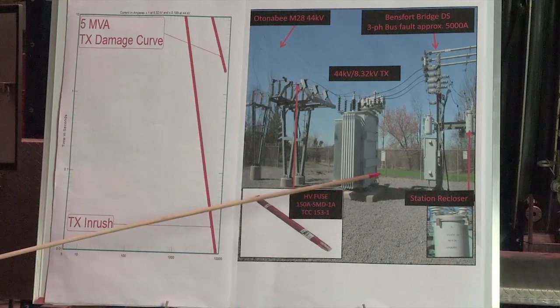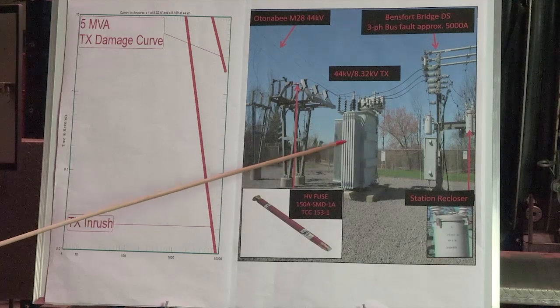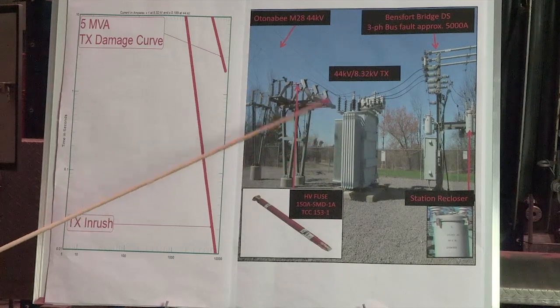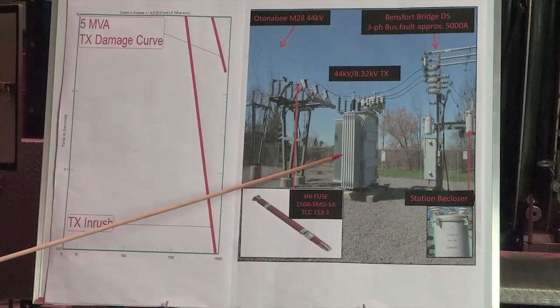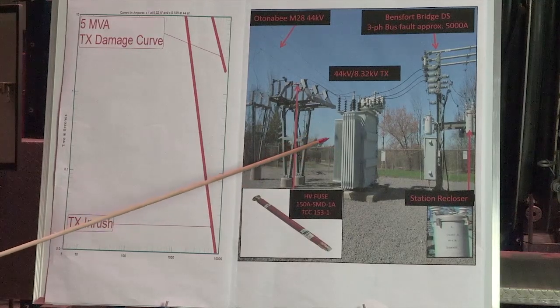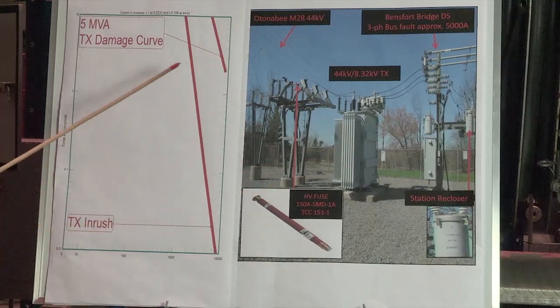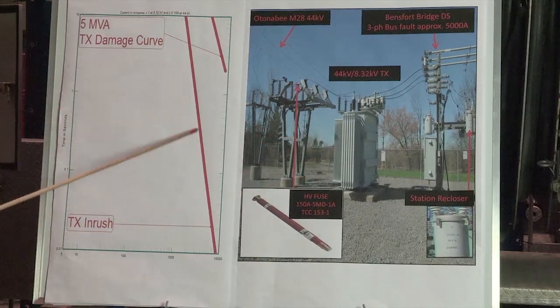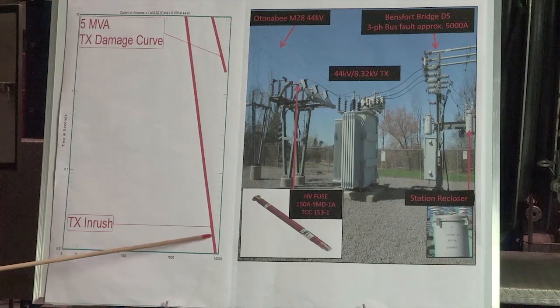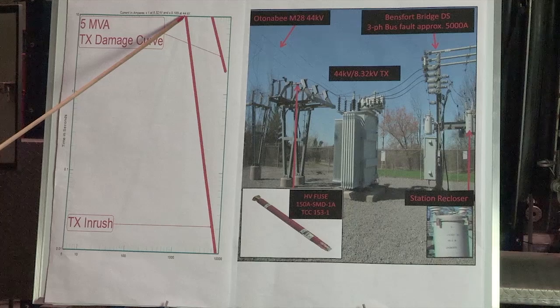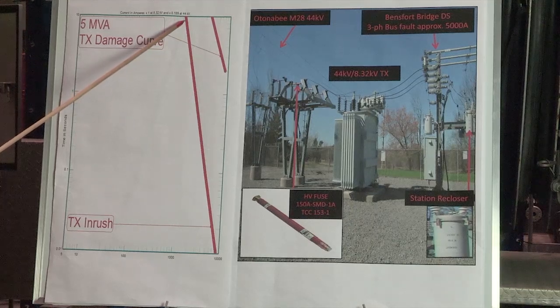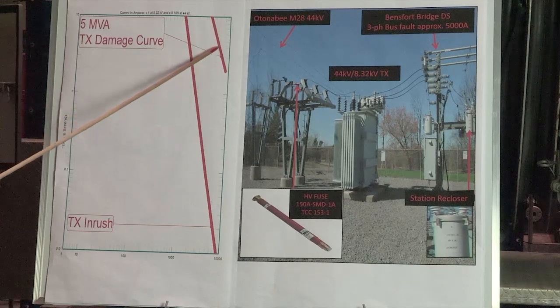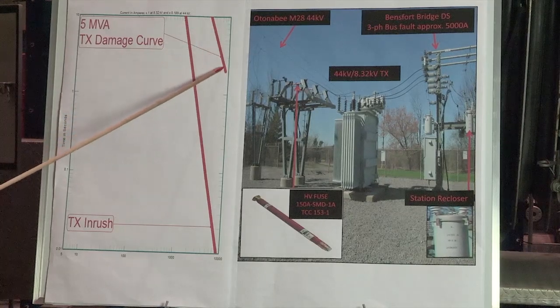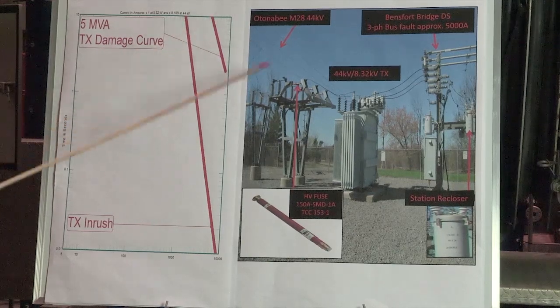So starting at the distribution station, we have Bensford Bridge DS. Now we're going to have to model in this transformer into a program that is called TCC, Time Characteristic Curves. So the diagram beside me is showing the transformer modeled into this program. And this here is the inrush curve of the transformer. This is a 7.5 MVA transformer, and this last curve, the curve that we're concerned with, is this damage curve at the DS. And I'll show you in a moment exactly how we need to protect this transformer from faults downstream or upstream from this DS.